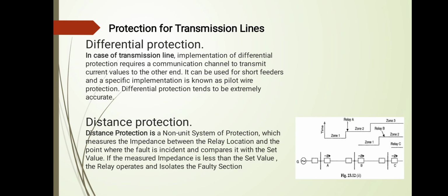We have two ways to protect a transmission line: differential protection and distance protection. For differential protection, in the case of a transmission line, implementation requires a communication channel to transmit current values to the other end. It can be used for short feeders, and a specific implementation is known as pilot wire protection. Differential protection tends to be extremely accurate. Distance protection is a non-unit system of protection which measures the impedance between the relay location and the point where the fault is incident and compares it with the set value. If the measured impedance is less than the set value, the relay operates and isolates the faulty section.